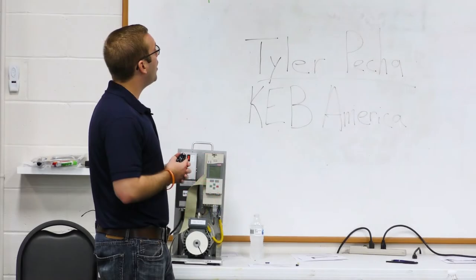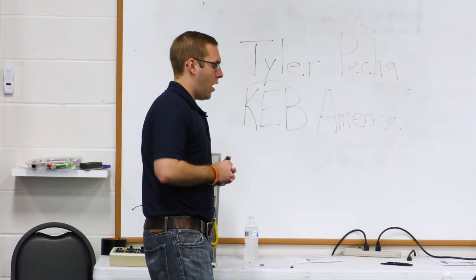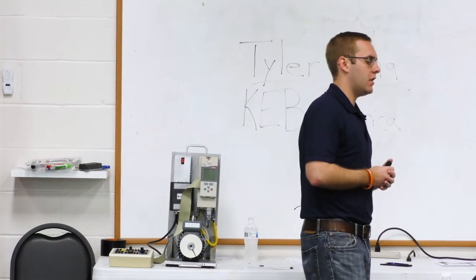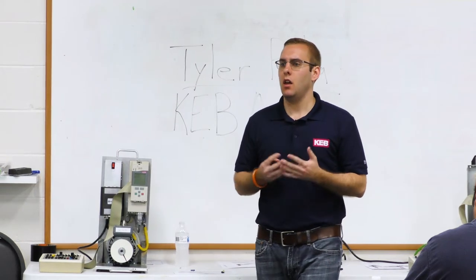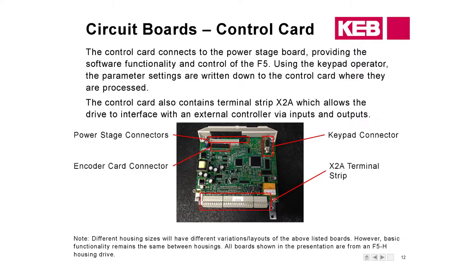Moving forward to the control card — this is the brains of the drive, where all the processing happens. It also contains the input and output terminal strip X2A, which is where you run all your hardware inputs and outputs. The keypad connects up in the corner, and it connects to the power stage via a ribbon cable run through a plastic guard. The encoder board also sits on top of the control card.